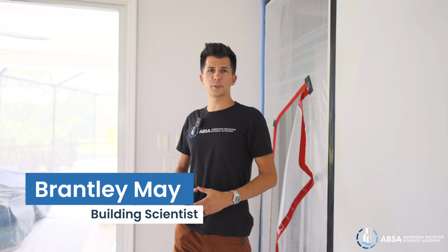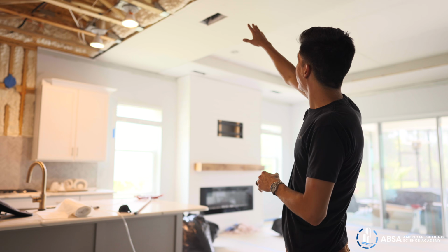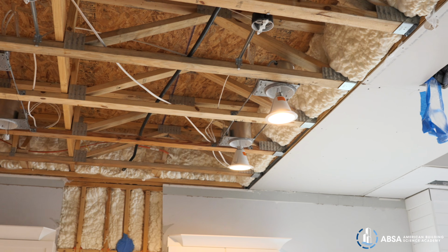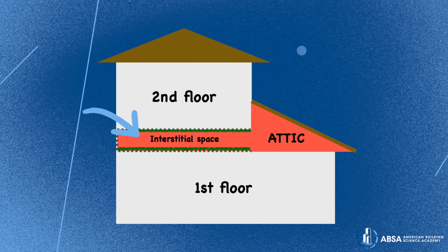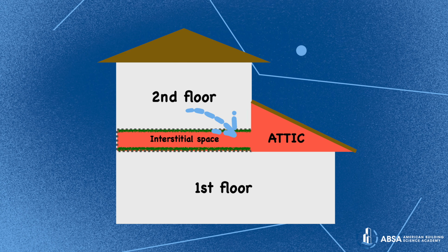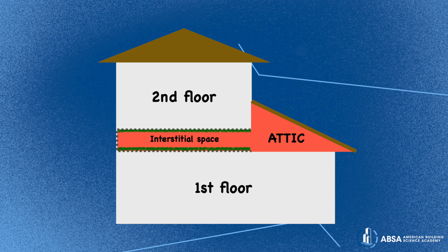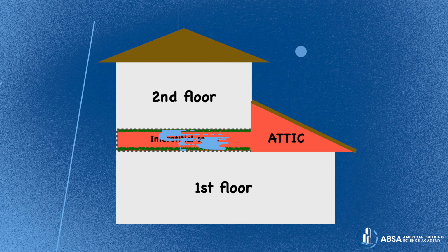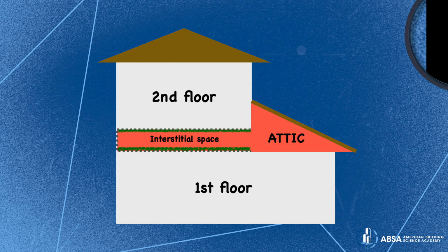Right, so they just finished up some mold remediation here a few weeks ago, and it's cleared now, the mold is gone. But what caused it was actually kind of crazy. So this attic space was opened up to this interstitial space. This is a space between a first and second floor. And so as that high dew point, high humidity air was coming into this space, it was causing mold growth on all the framing and even the ductwork.